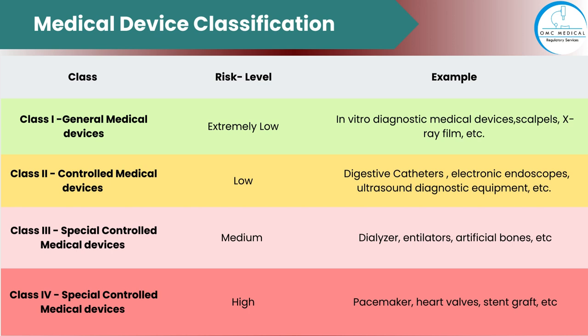Class 1, general medical devices, which are the lowest risk devices. These devices are typically used for non-invasive procedures and pose little risk to patients. Examples of Class 1 devices include X-ray film, scalpels, and certain in vitro diagnostic devices.